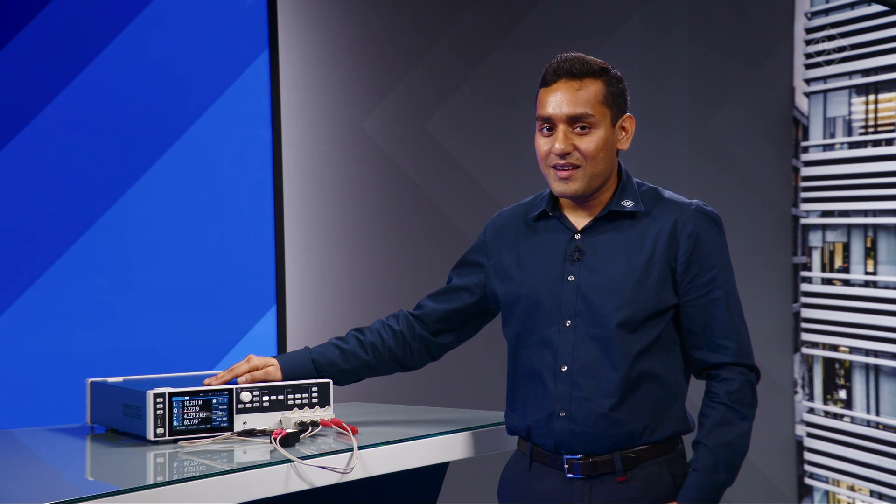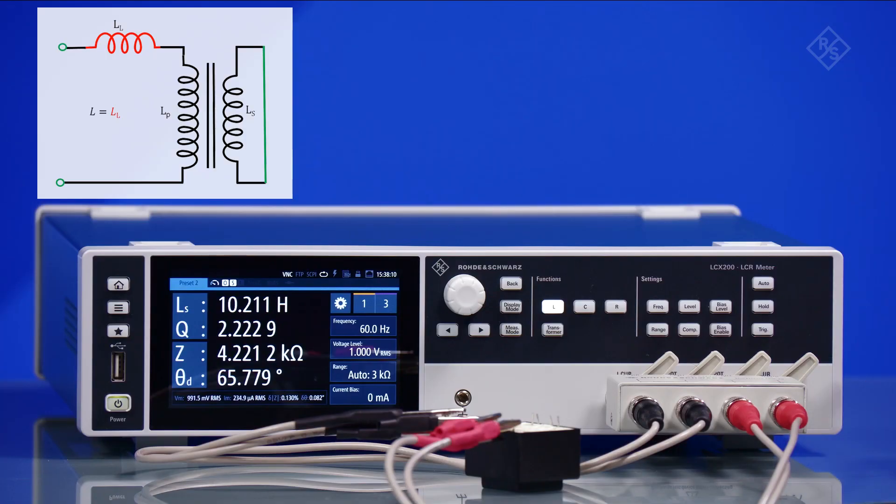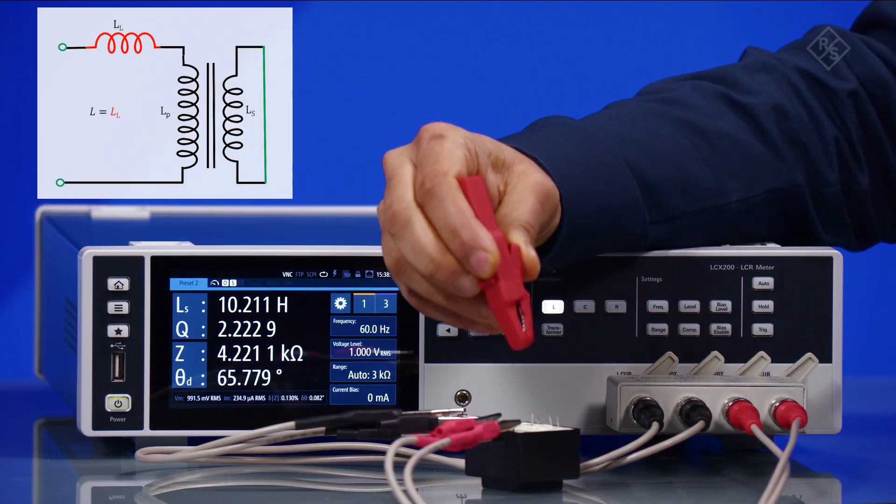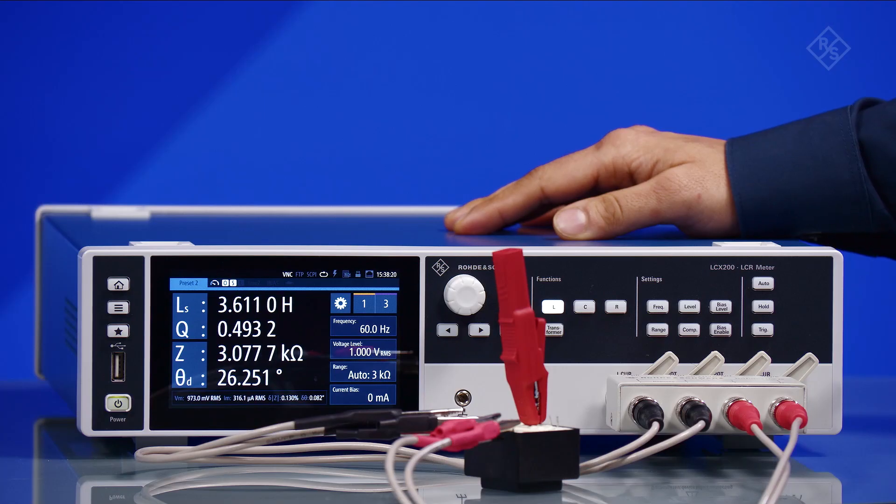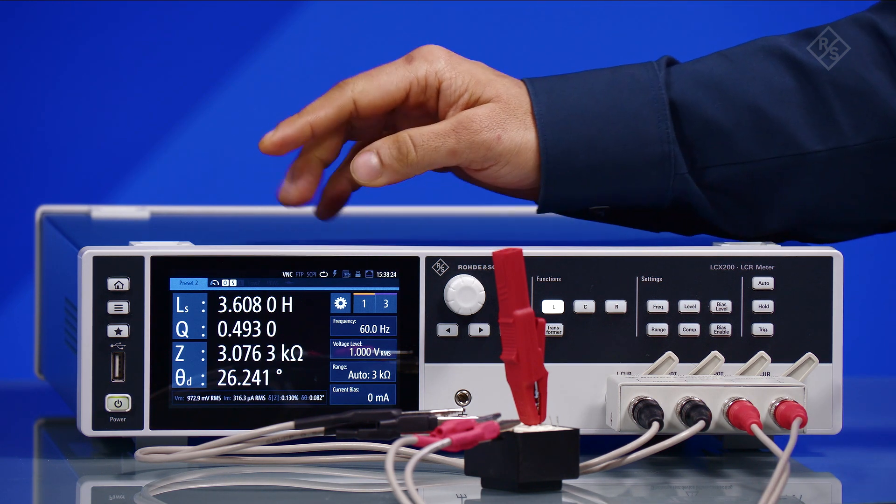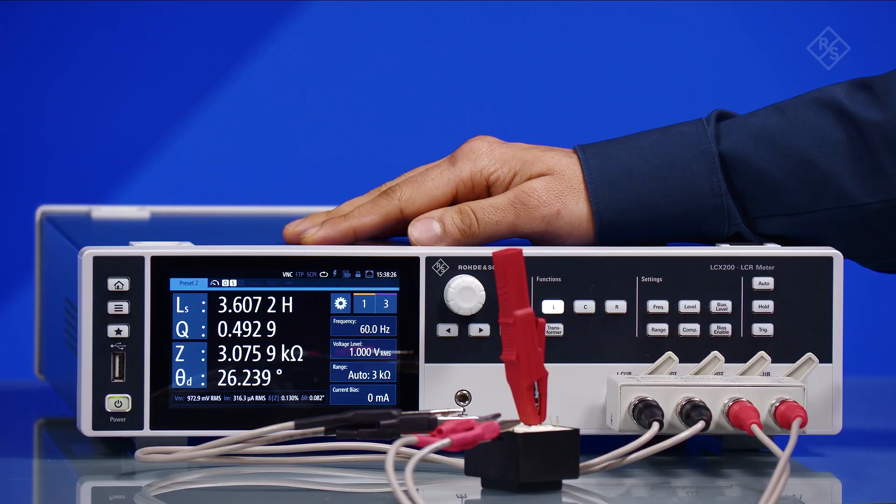Now let us have a look at how to do a leakage inductance measurement. The connections and measurement settings for the leakage inductance measurement are the same as for the primary inductance, except that the secondary winding in this case is shorted using a safety alligator clip. The measured inductance value on the screen now corresponds to the primary leakage inductance.